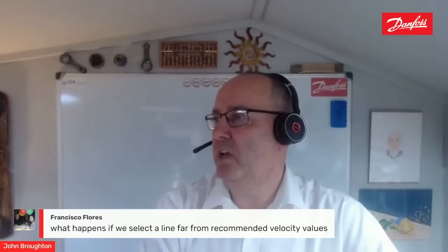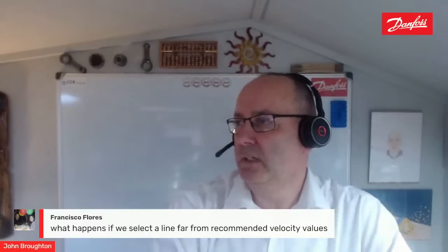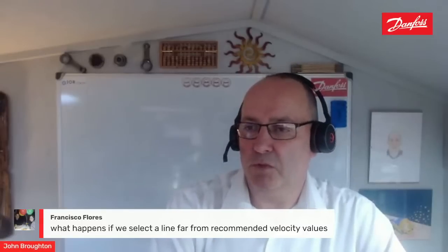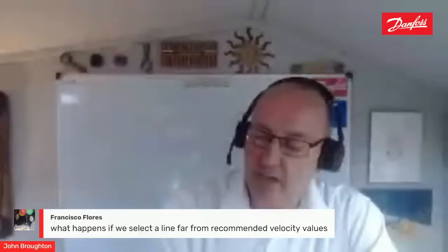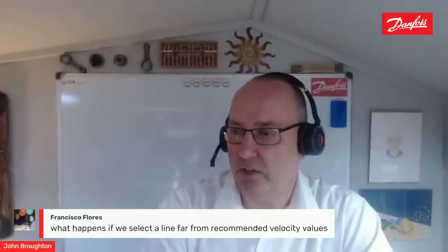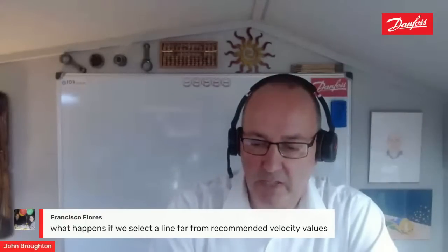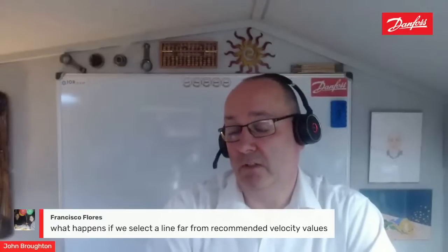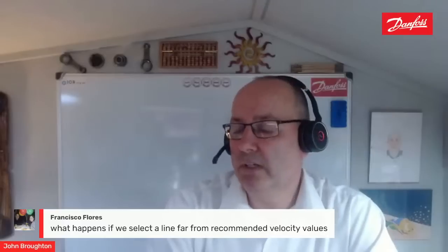There's a question up from Francisco, and that is a YouTube question. He says, what happens if we select a line far from recommended velocity values? Well, that comes back to what we discussed previously. If we talk about a liquid line at high velocity, then we'll get noise in the system, and you'll hear that as a whistling noise. You can also get pipe movement on a liquid line. You can also get pipe movement on a suction line.